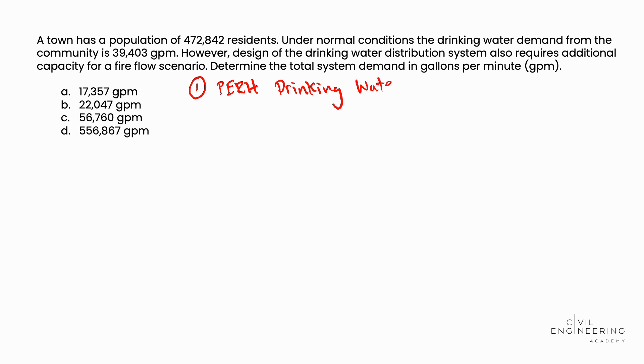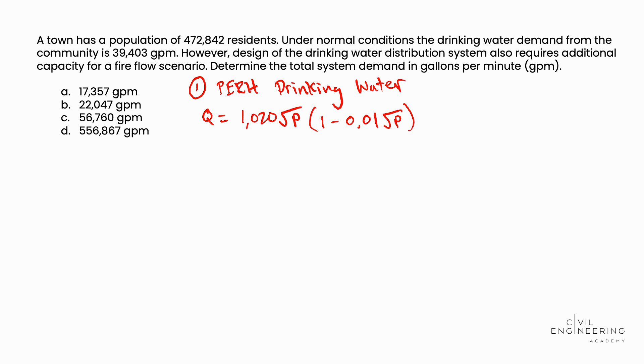we see there is an equation called the National Board of Fire Underwriters Equation. That equation is: Q (flow rate) = 1,020 × √P × (1 − 0.01 × √P). We need to be careful here because P in this case is population, but it's in thousands. So we need to be careful about that.